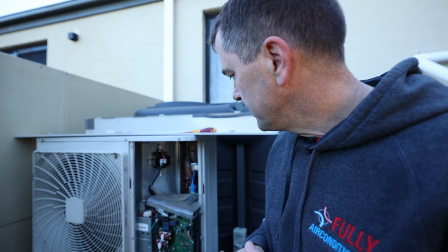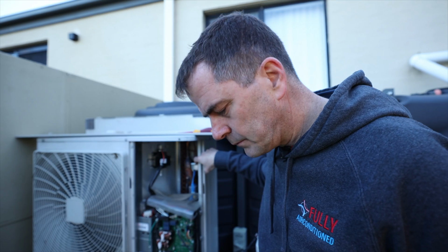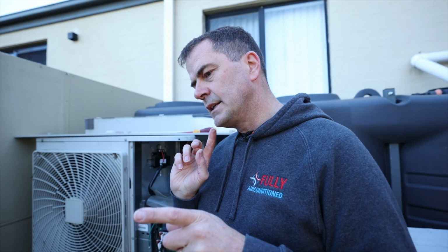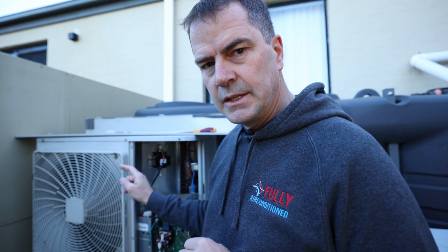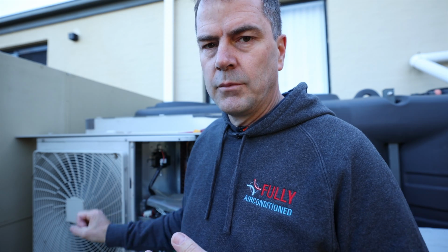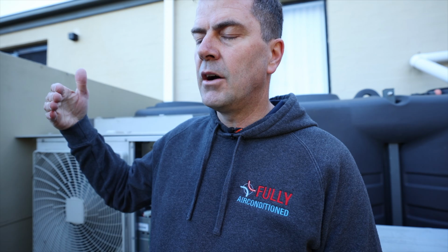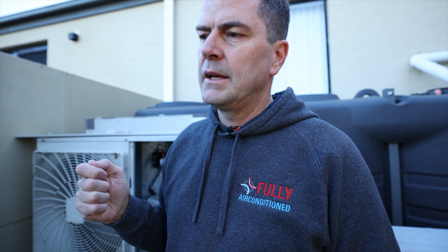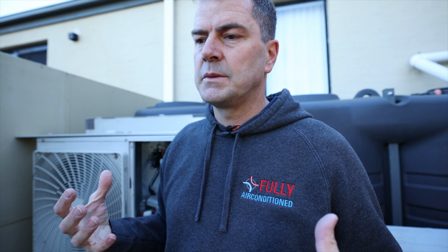The reversing valve, which is this thing here, reverses the gas flow. It sends the cold gas inside this time and the hot gas outside to the outdoor coil. The compressor continues to run, and it will run and melt all the ice. Yes, we're sending cold gas to the indoor, and that's why we turn the fan off. It does absorb some heat from the indoor unit.